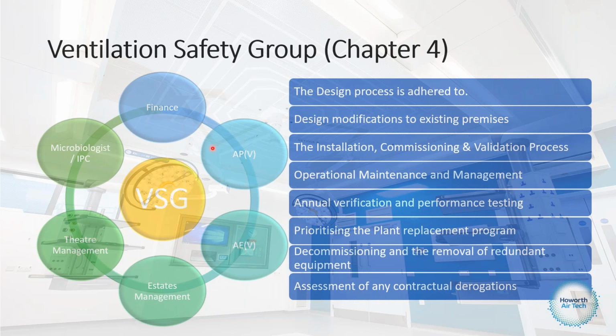And the reason this is my favourite bit is because as a subcontractor, we were constantly asked if the space could be used or it was fit for purpose, which we can't make that decision. It needs to be a decision by the VSG. We're engineers, we're not clinically led on or IPC or microbiologists. So the way that this would work is, as a subcontractor, I would sit out of the circle here, I could tie in at various points, but this would be my main point of contact more often than not, the AP for vent.